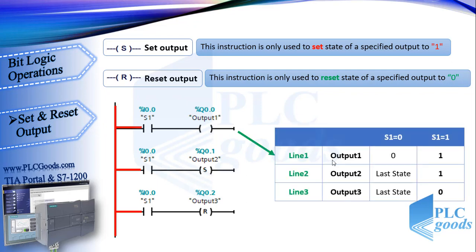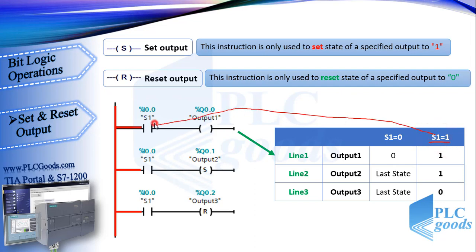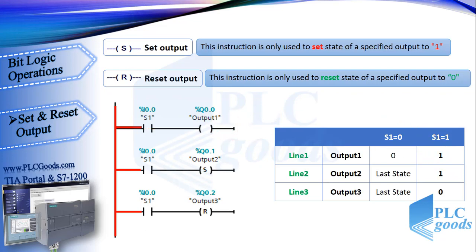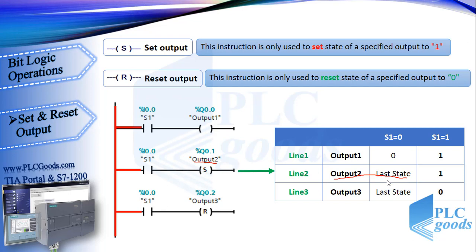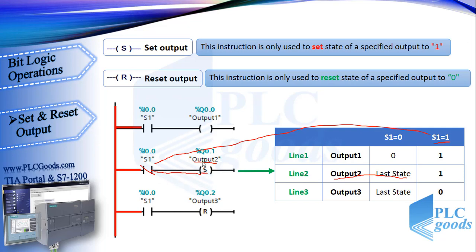First line has been explained in previous slide. When S1 is zero or inactive, the first output will be off. If the S1 contact is activated, its state is changed to close, then first output will be on. Now see second line which has used a set instruction. When the set is not activated, it won't do anything, so second output holds its state. It means if second output is zero, it will remain zero, and if it is one or activated, it will be one. When S1 is activated and changes this contact to closed, the virtual power reaches to set instruction, and then this instruction activates second output, either it be zero or one.